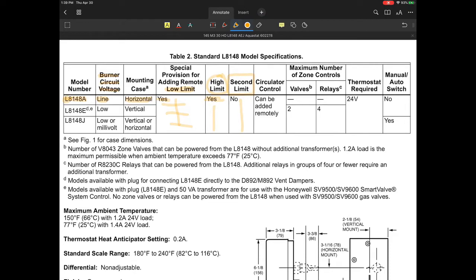As far as circulator control, it says it can be added remotely. That could be something where you can control this, but typically the actual relay on the Aquastat will give you a set of contacts to control this. So what they're telling you is it can be added remotely, but technically it is dictated by the T-stat input. When there's a T-stat input, it tells that relay, hey, we need the circulator running. The other part of what they're talking about is even a low limit control as well. And again, we'll look at that in a little bit.